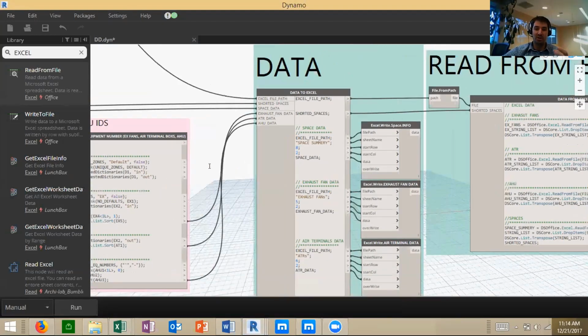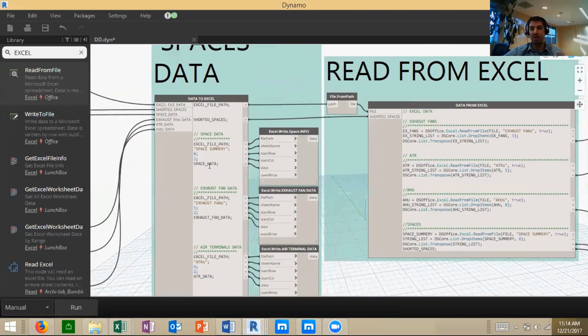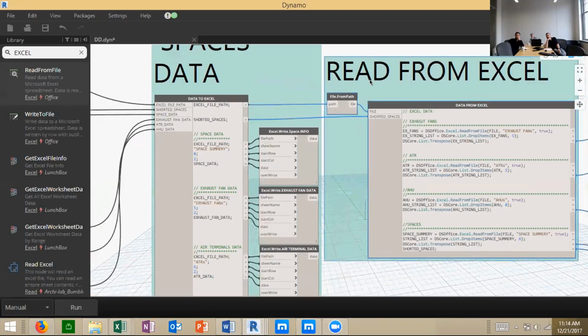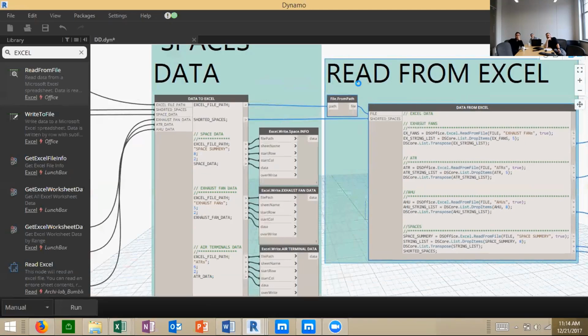automatically and update them automatically. So if you make a change in the air balance table in Excel, then your Revit will update. If you change zoning in Revit, your Excel will update, which in turn will edit and update the other schedules in Revit accurately. Yeah, that was the main thing.